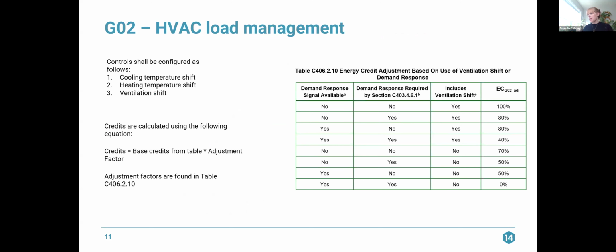G02, HVAC load management, requires controls that are configured to provide a cooling temperature shift, a heating temperature shift, and a ventilation shift. We'll go through what those are required to be on the next slide. The credits are calculated using the following equation. The credits you achieve equal the base credits from the table times the adjustment factor. And the adjustment factors are found in table C406.2.10. That adjustment factor is right here.